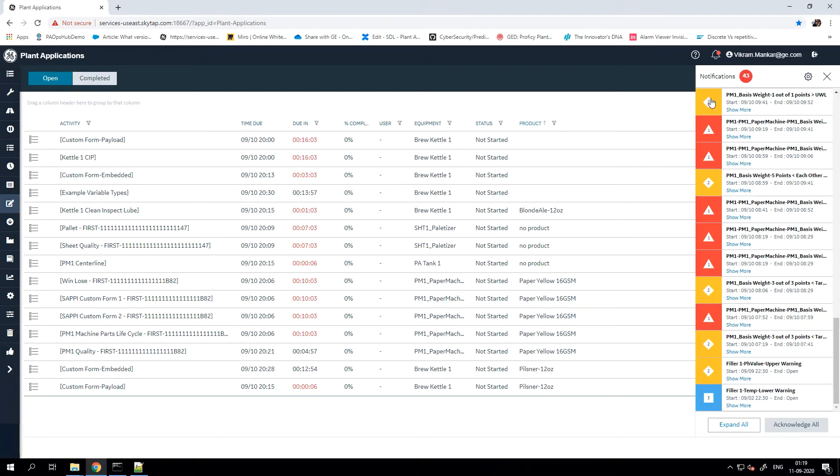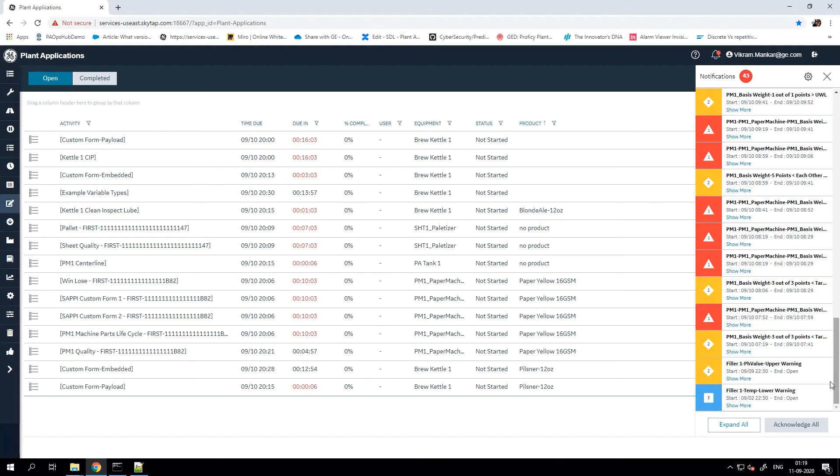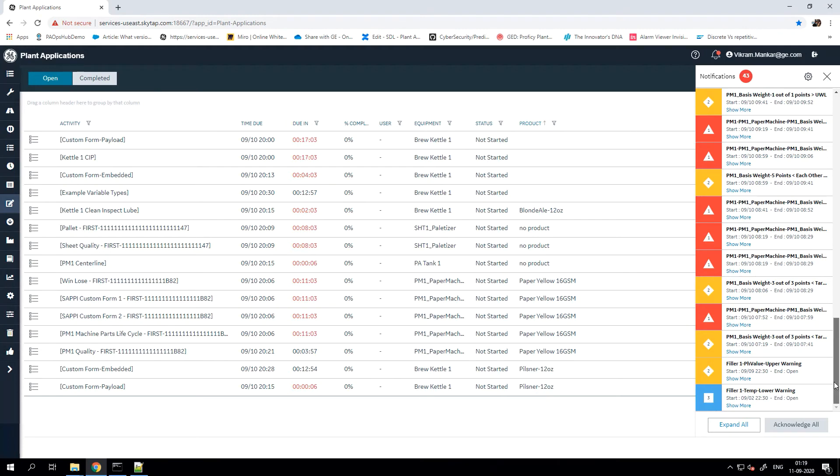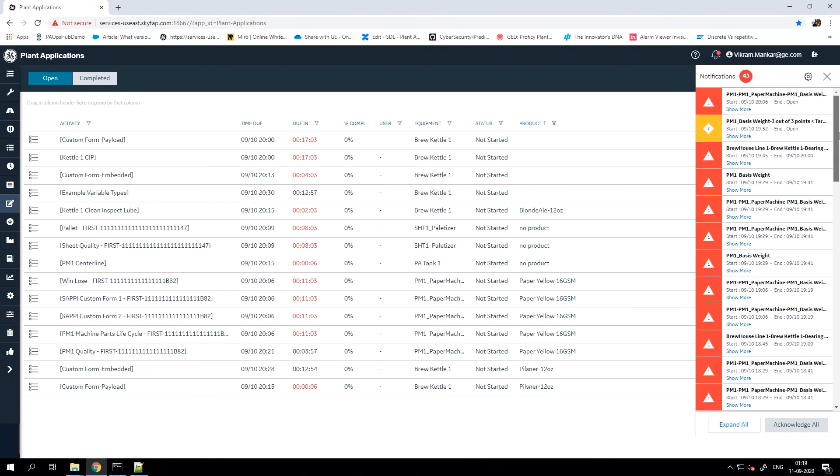You will also see different color schemes here. The red box with the number one in a triangle represents the high priority alarms. The yellow box with the number two represents medium priority. And then the blue box with the number three in it represents low priority alarms.